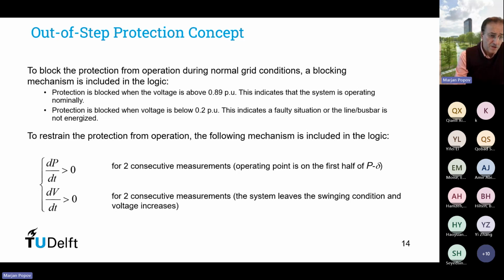Here, I'm going to explain why the protection should be blocked or restrained. So the protection will be blocked whenever the voltage is above 0.89 per unit, which means that normally in electrical power systems, the voltage may drop by 10%, so if the voltage is above 89%, in that case, the protection must be blocked. This is not an out-of-step condition. The protection will also be blocked when the voltage drops below 20%, 0.2 per unit. This indicates a faulty situation or the line busbar is not energized. Well, if it's a faulty situation, then the out-of-step protection also must be blocked because it is not the goal of the protection to eliminate faults. There is another protection solution which is used to eliminate faults, of course.